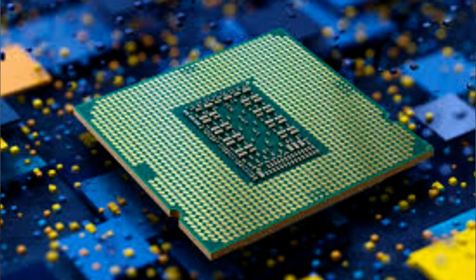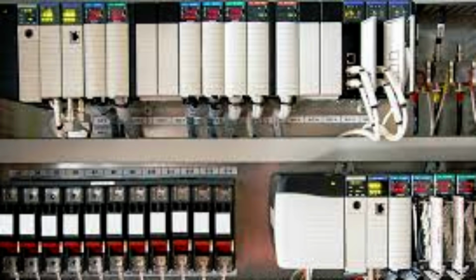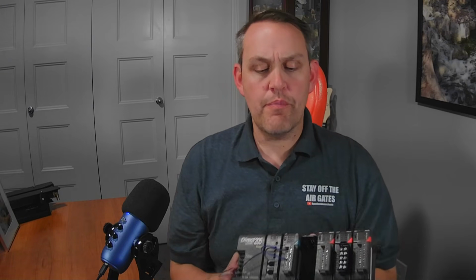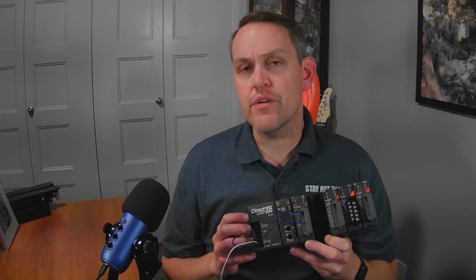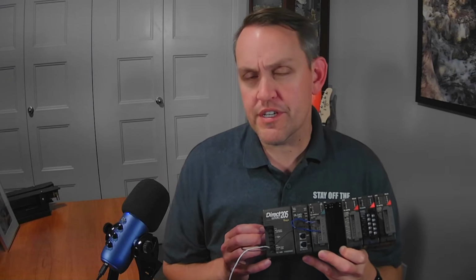Computer processors are able to execute programs and calculations, essentially. We used a processor to write a program, and then gave the program another program to run, and now we have the programmable logic controller, or PLC for short. These PLCs use internal logic instead of relays and miles of wiring like its predecessor did. It's all contained in this neat little package mounted inside a control cabinet somewhere inside the ride. The PLC is essentially divided into 3 basic types of modules, of which I'll touch on some of them, but there's thousands of combinations out there, so I don't want to get too deep into any one particular thing.